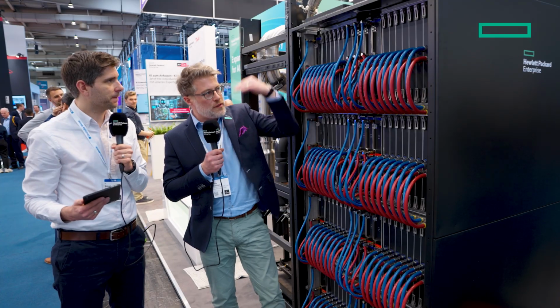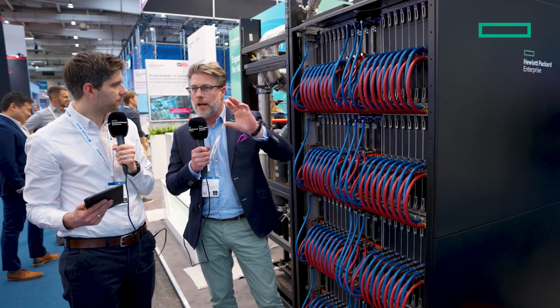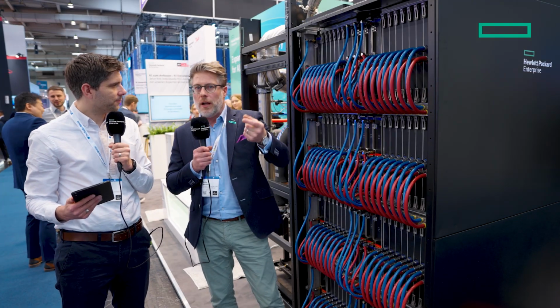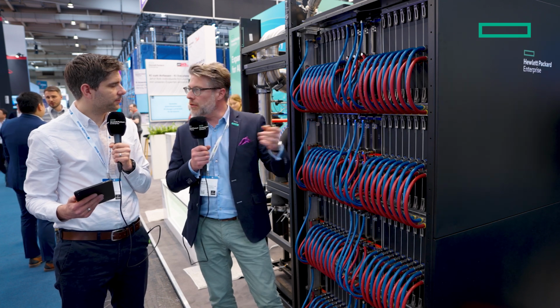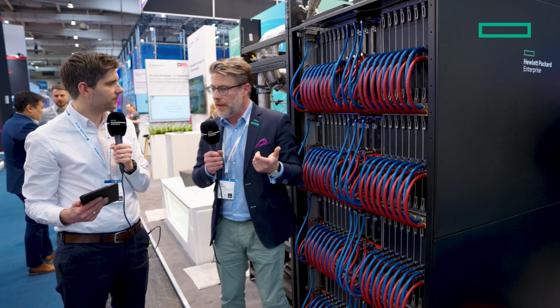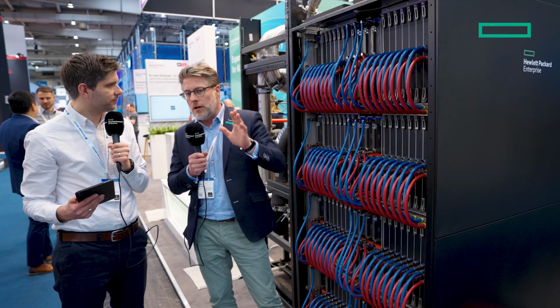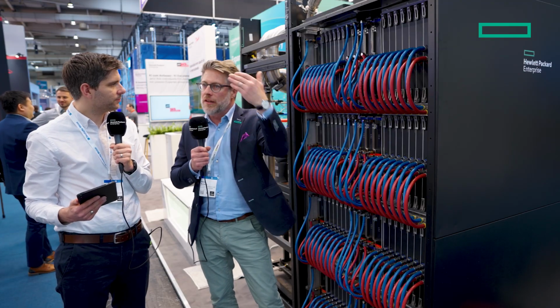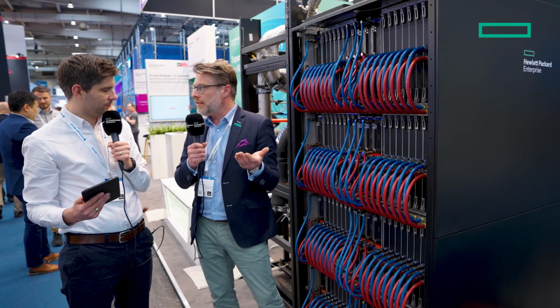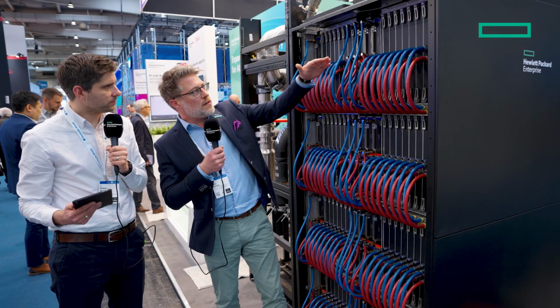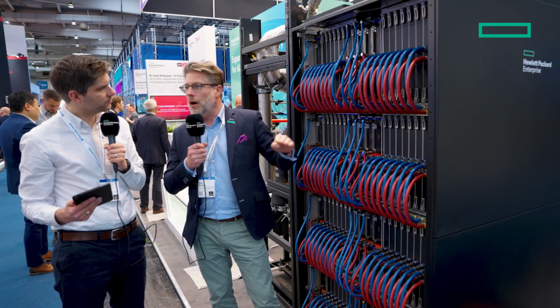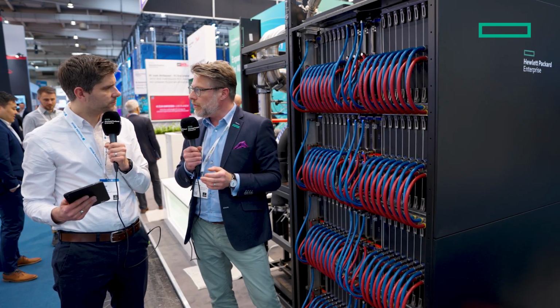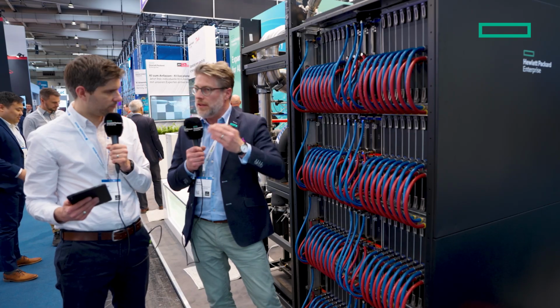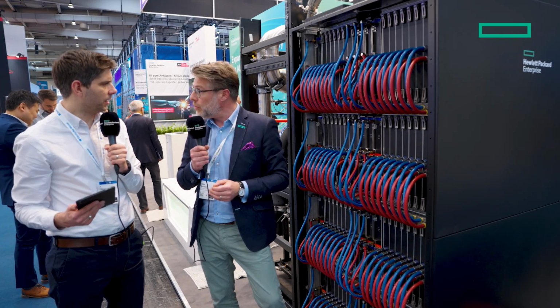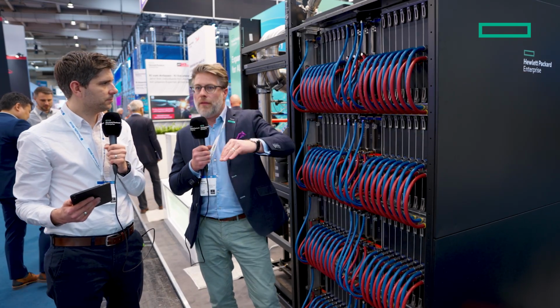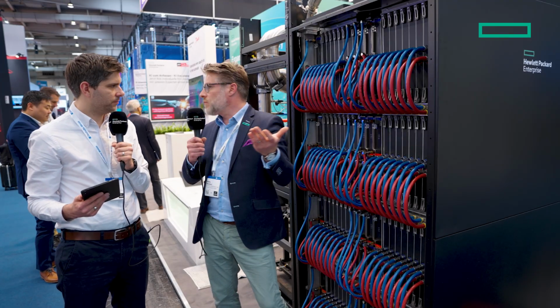We have one series below, the HPC series, that we call hybrid. So you still have the largest portion direct liquid cooled - like the processors and stuff - but still a portion of 25-30% needs to be air-cooled, as classically in data centers. One series below that is around 150 kilowatts in a rack, hybridly cooled, still with a bigger direct liquid cooling portion. And then the ones below, it's classical air cooling.